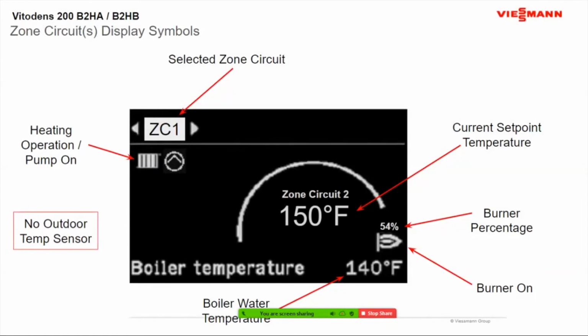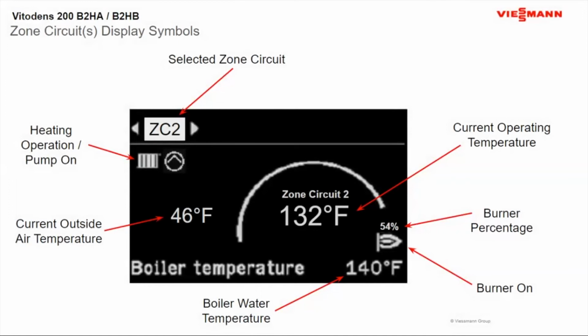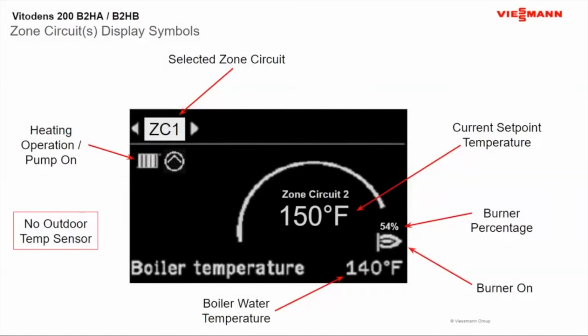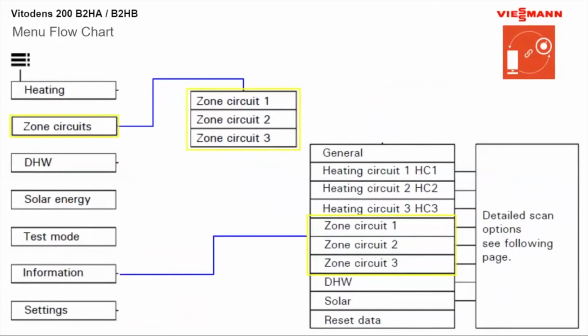Next one, now you can see zone circuit 1. Now you can see that the radiator's on. Our pump is on, but now you don't see the outdoor temperature. Remember, in the prior screen we had the current outdoor temperature, because we're doing weather compensation there. Whereas this one here, we're doing a fixed set point. If you hit the zone circuits, you can see what they're doing and how they're set up. And then under information, you can see what they're doing, the actual set points.